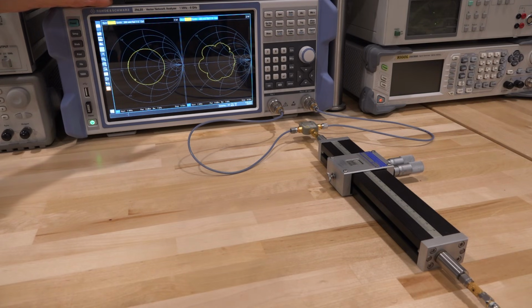This is exactly what I've done here. In common mode calibration, the instrument can compute common mode versus differential S-parameters to give you mixed mode S-parameters, so you don't have to use an external transformer, for instance. This is very useful and of course can be done because these are linear systems.